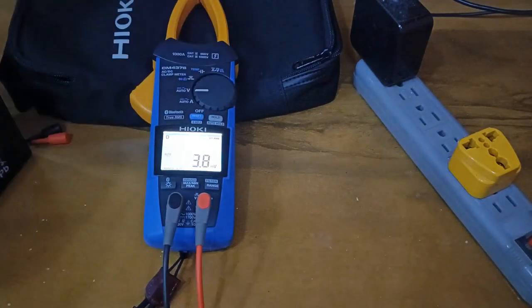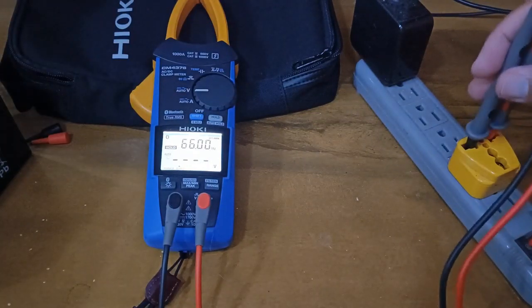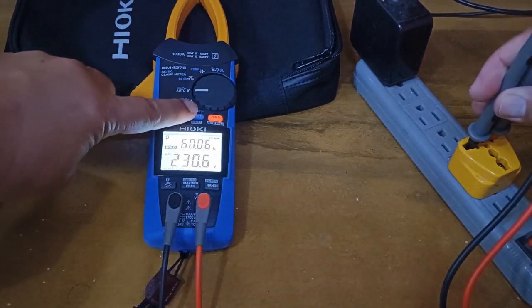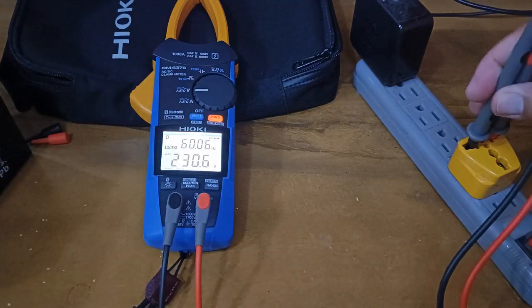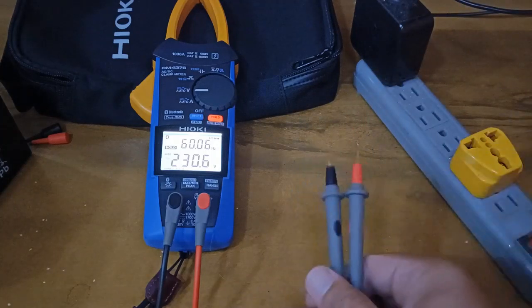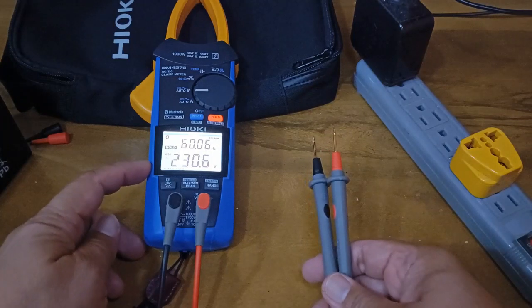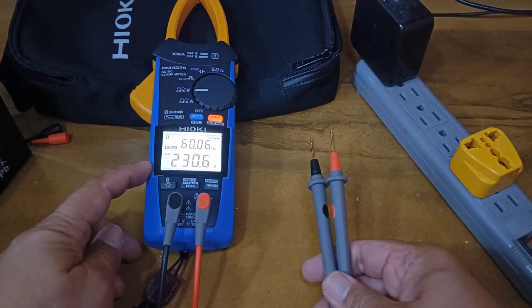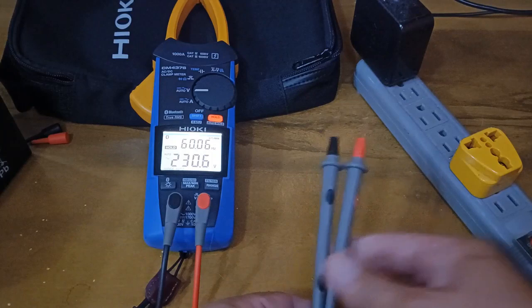Using the auto hold function at the voltage measurement, once the value stabilizes, the hold button flashes red, and now I can remove the test leads from the test points and simply read the value that is retained on screen. That's 230.6 volts AC, 60.06 hertz.